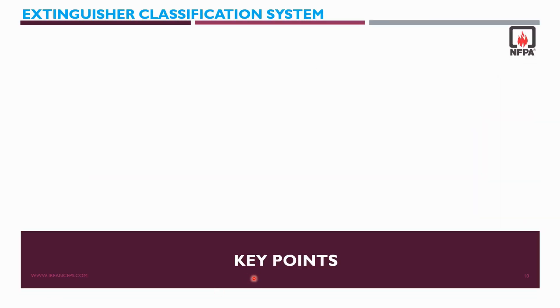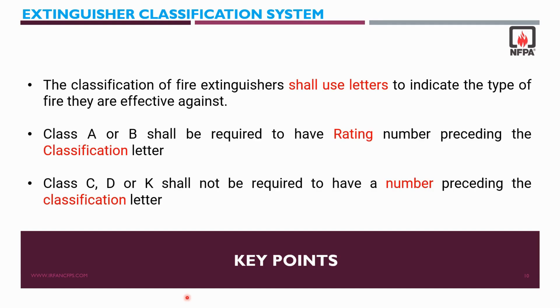Before we move ahead, we shall discuss the key points of extinguisher classification systems. The classification of fire extinguishers shall use letters to indicate the type of fire they are effective against. Class A or Class B extinguishers shall be required to have a rating number preceding the classification letter. Class C, D, or K shall not be required to have a number preceding the classification letter. These are the three key points to remember when defining extinguisher classification.